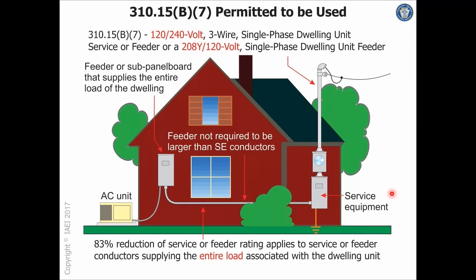Now in a case like this, I can size these service entrance conductors and that feeder because that feeder's panelboard does provide power to the entire dwelling unit — the AC is coming out of it rather than out of the service equipment over here. So I could use that 83% load calculation on that feeder in a case like this.